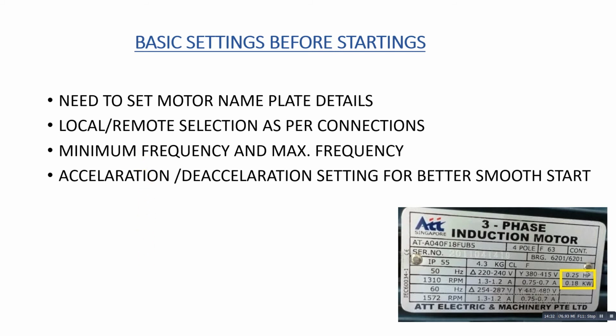Okay, some regions use 60 and some regions use 50. So you have to make sure of your nominal frequency rating. Okay, and also set the acceleration and deceleration settings for a smoother start. So even if it is starting from 0 to full speed, that speed level you can adjust by timing.